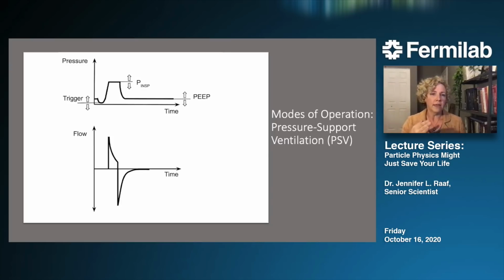And the way the exhale begins is when the flow has dropped below a given fraction of the peak flow. When it drops to 30% of whatever the peak was, then the MVM valves will change state and the exhalation is allowed to begin. And then the machine goes back to waiting for another inhale trigger. If the patient takes too long to inhale again, that's called an apnea, and the system will go into alarm and force a breath, switching back to PCV.